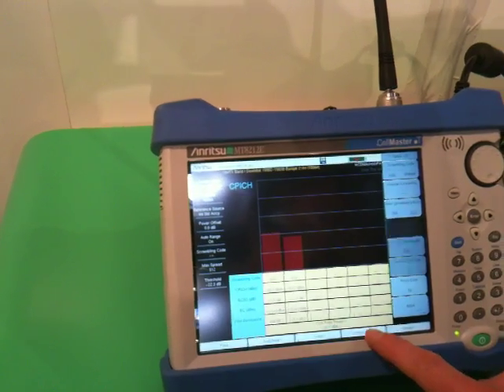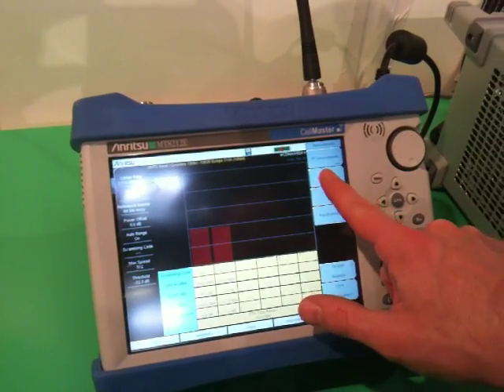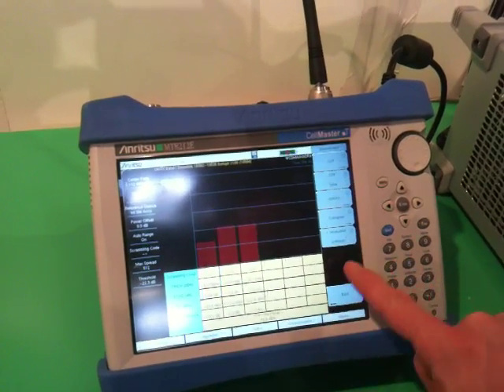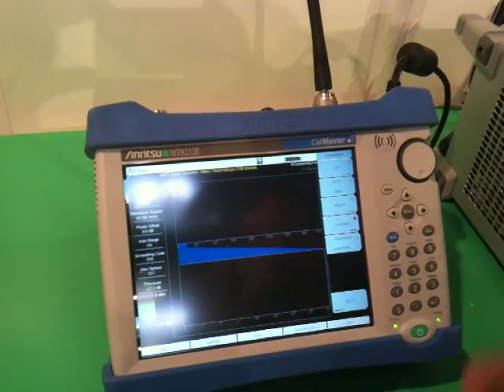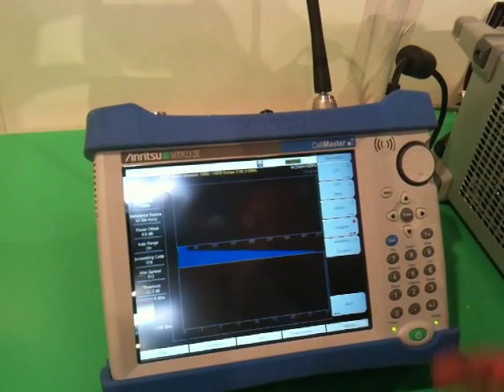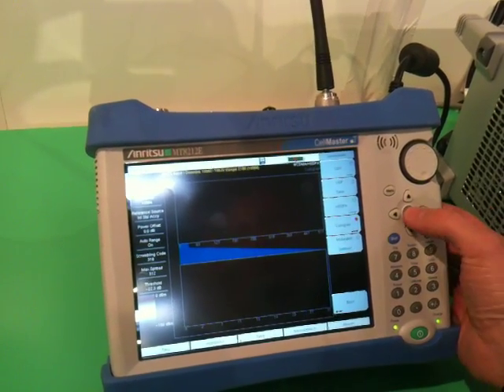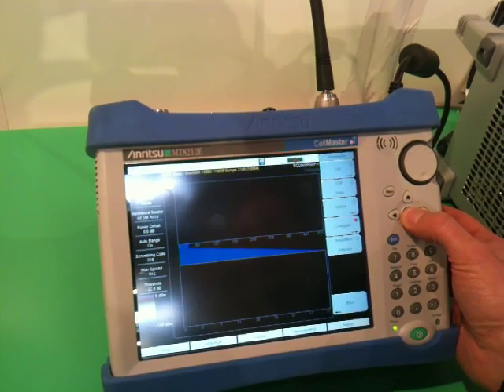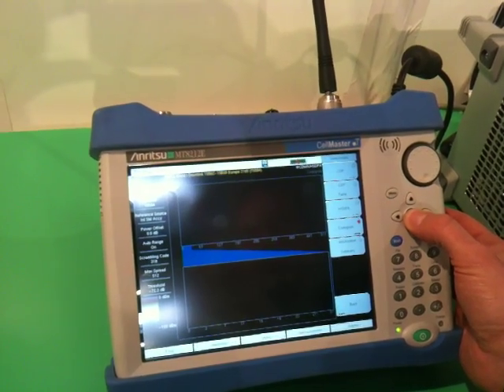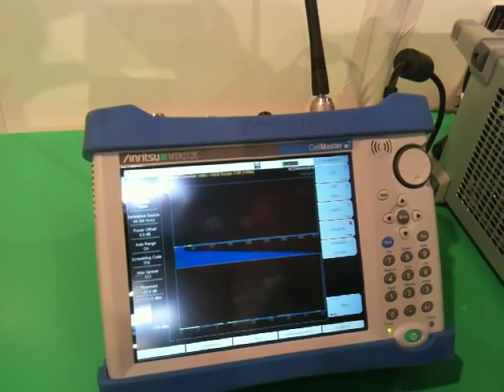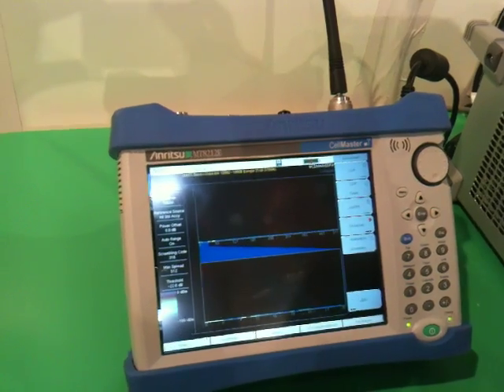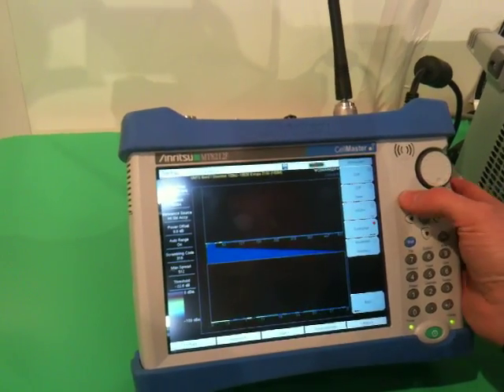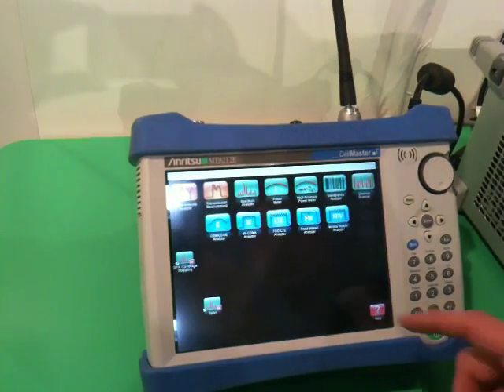I can choose my different measurements using touchscreen technology and start to do different sweeps. And then if I like a measurement, I can hold it down and make a record of that measurement. It's a really good innovation in how I would use equipment out in the field.